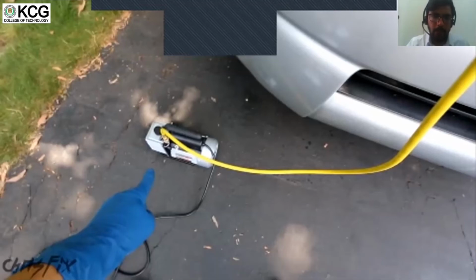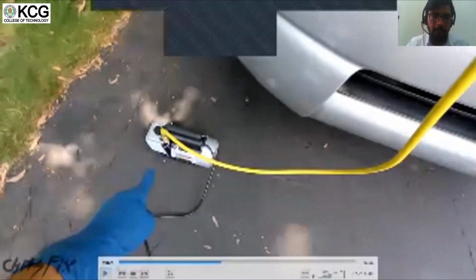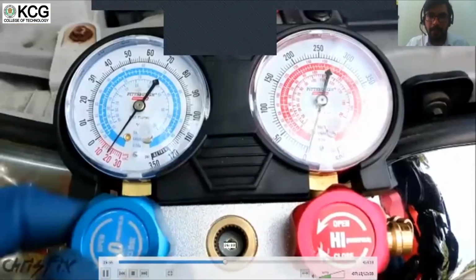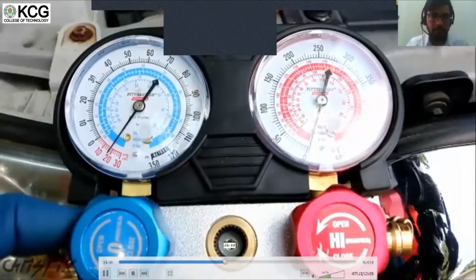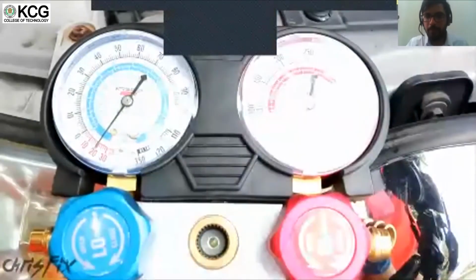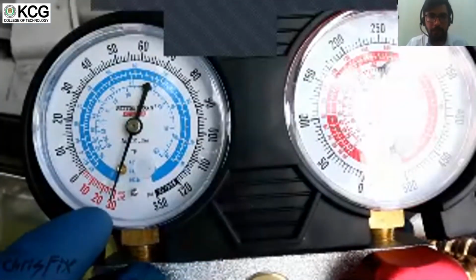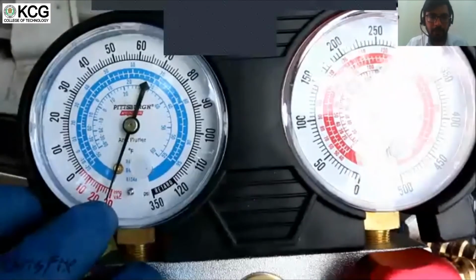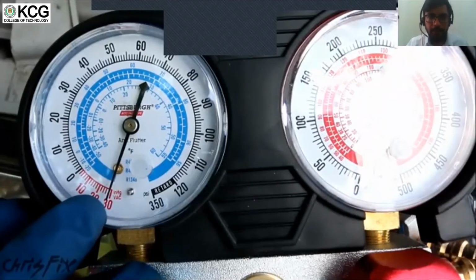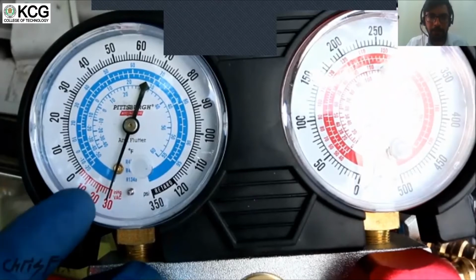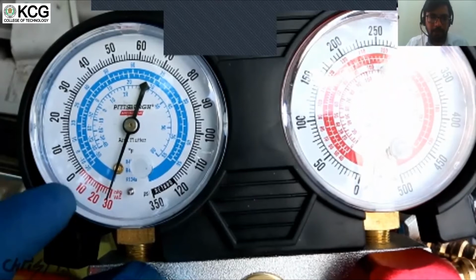So as you can see, the vacuum is building. Let's go turn on the low pressure gauge. I'm just going to be focusing right here because this has the vacuum on the gauge. Even though this goes below 0, it doesn't have the actual readings. And you can see we're almost at 30 inches of mercury for vacuum, which is exactly where we want to be. So after letting this run for a few minutes, there's just about 30 inches of mercury of vacuum.